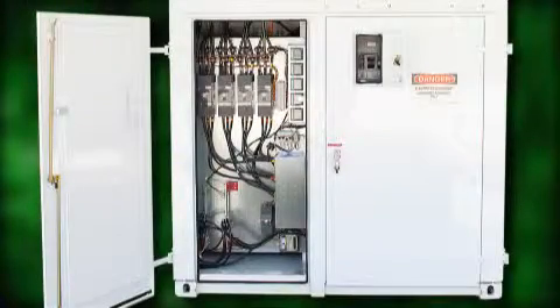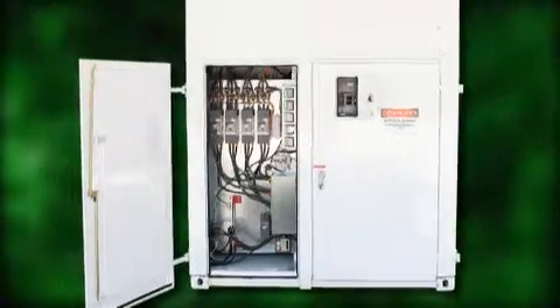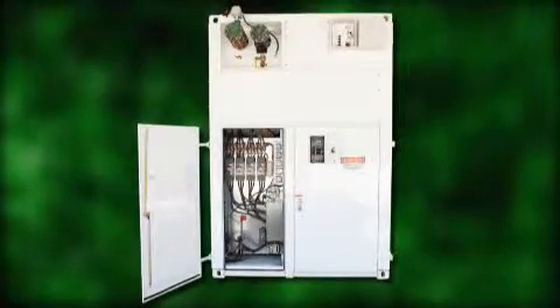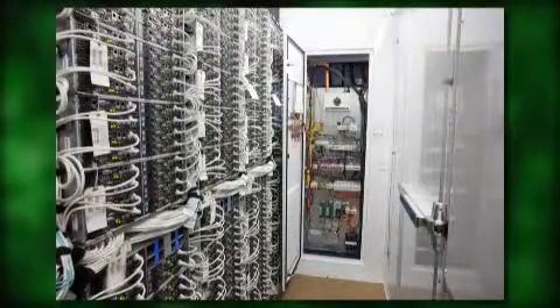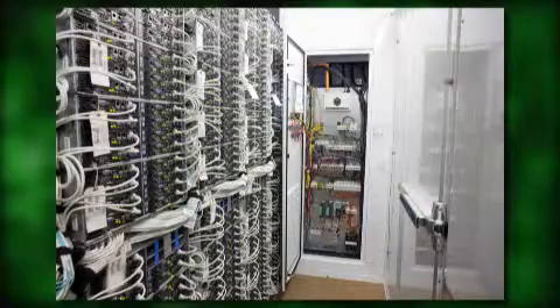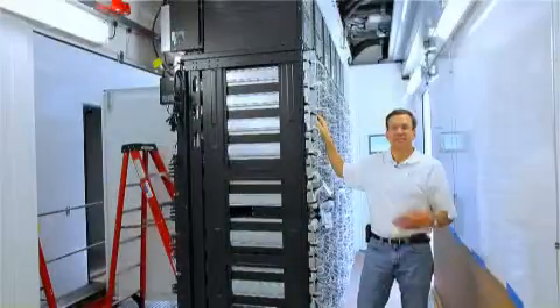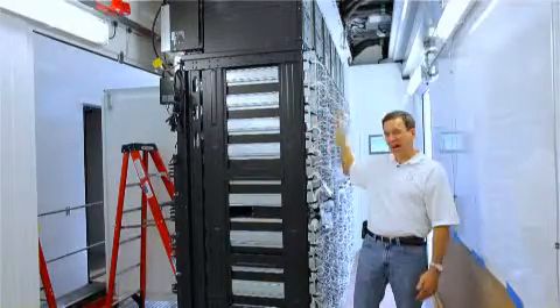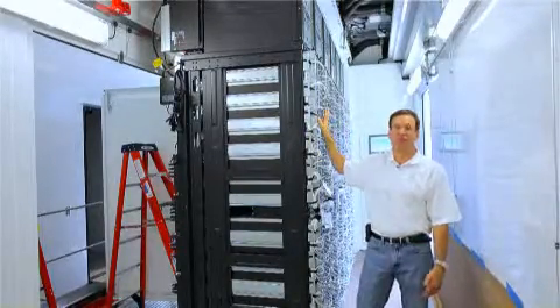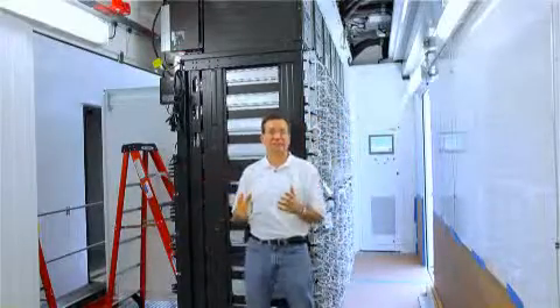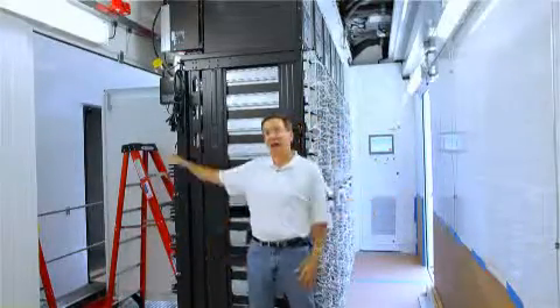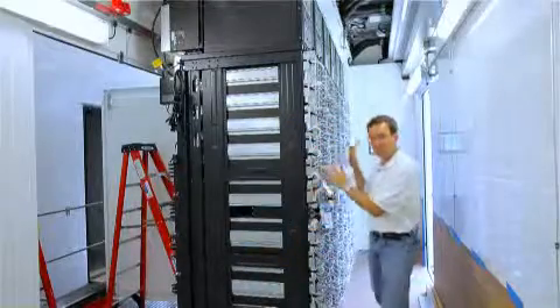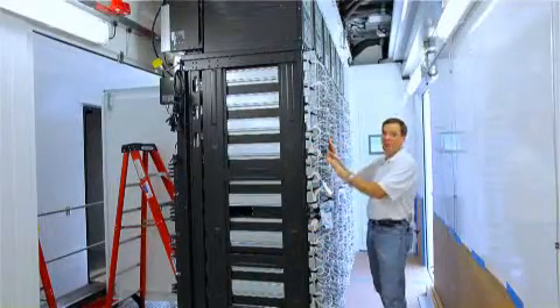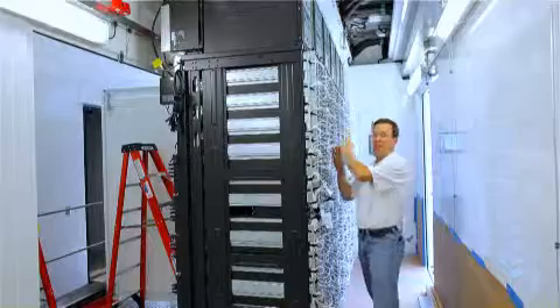It's about optimizing around your need for IT flexibility within typical available power footprint. That means multiple densities, multiple tier levels, worldwide availability, right when you need it. This is about your need to use IT to serve your customers. Operationally, your team sees this as a row of IT just like a data center, with a cold aisle and a hot aisle. Yet the racks are pre-tested, pre-wired, whether it's one pod or multiple pods, all the way out to 3 megawatts.